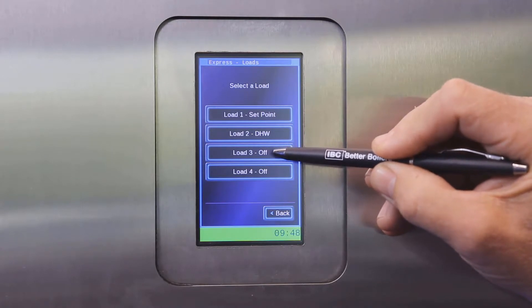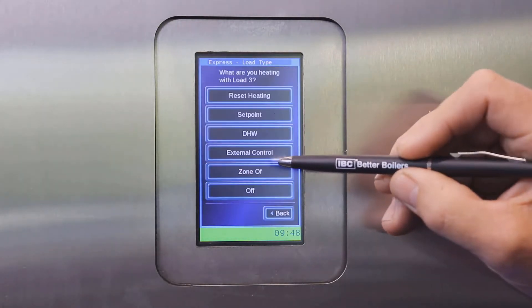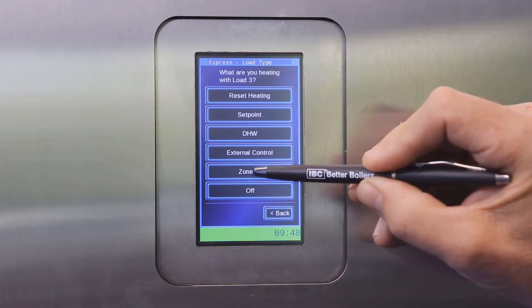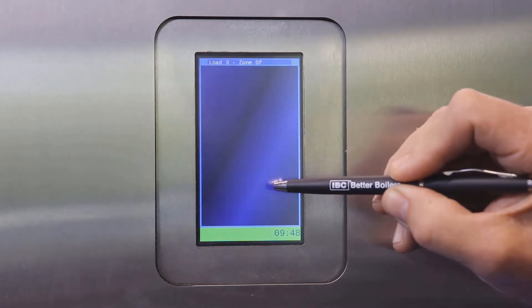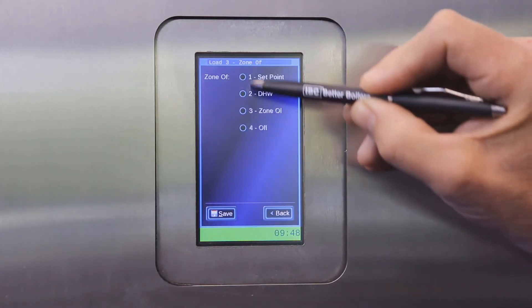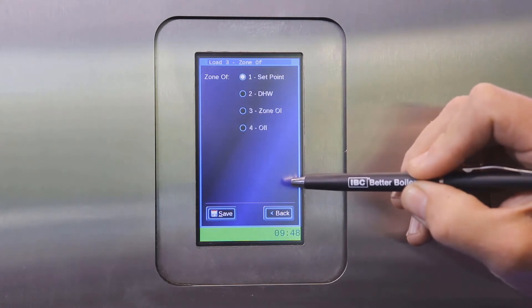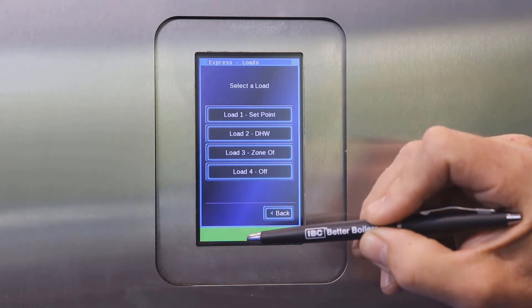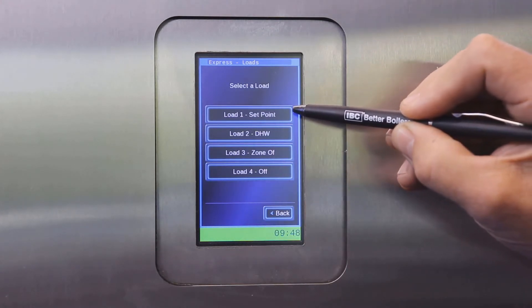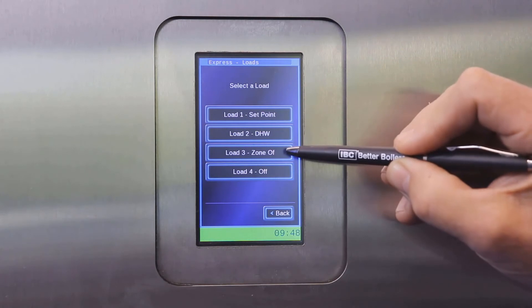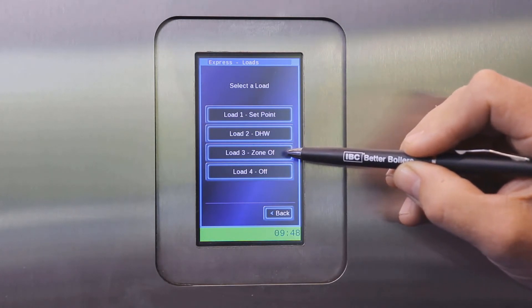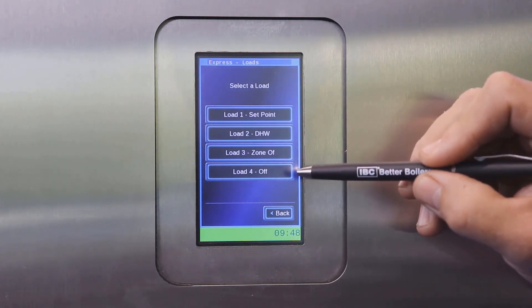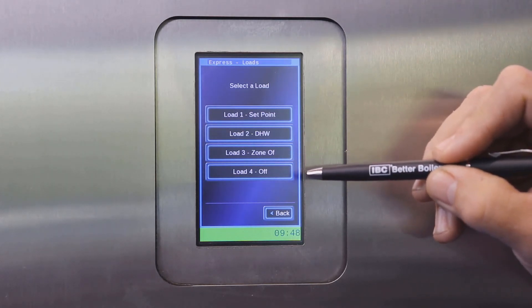If we then want to set load 3 as a zone of load 1, the setpoint load, we then tag it as a zone of and we choose which load we would like it to be a zone of and then save. Whenever there is a call for heat on load 1 and load 3, the loads will run simultaneously or individually at a setpoint of 130 Fahrenheit.